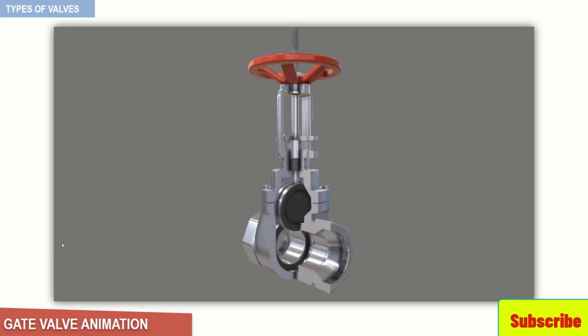When the valve is fully closed, a disc-to-seal ring contact surface exists for 360 degrees, and good sealing is provided. With the proper mating of a disc to the seal ring, very little or no leakage occurs across the disc when the gate valve is closed. A gate valve can be used for a wide variety of fluids and provides a tight seal when closed.